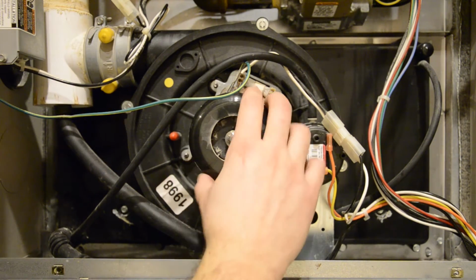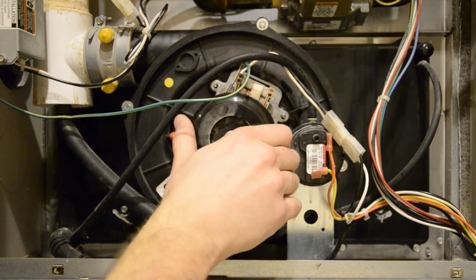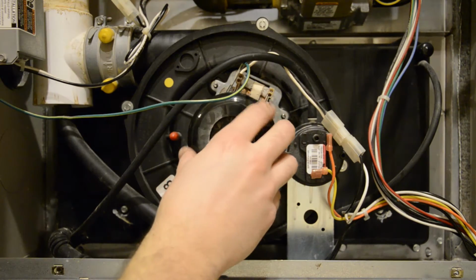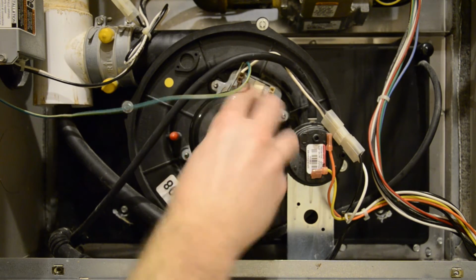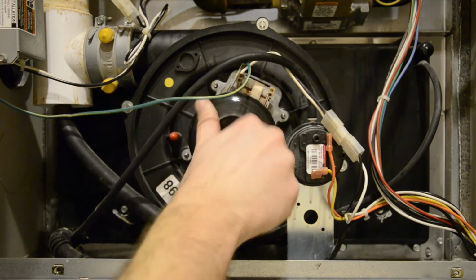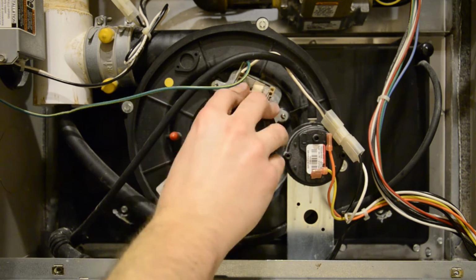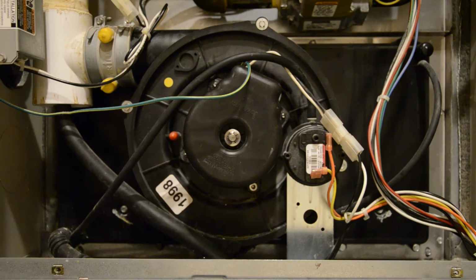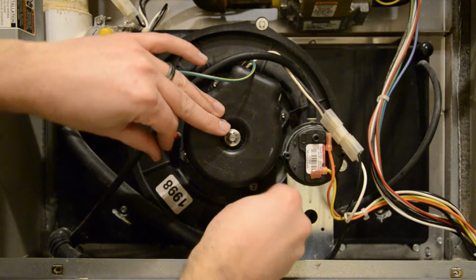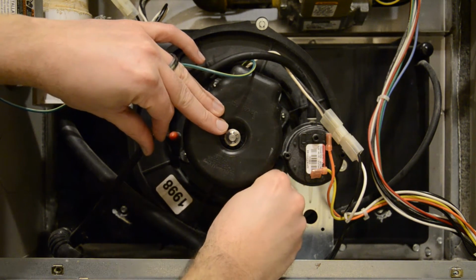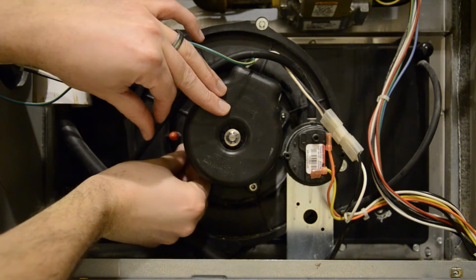Try turning the motor to see if it's stuck. If not, you may be able to temporarily reseat the bearing by turning the motor many times and retightening everything. Put the cover back on and reinstall and tighten the 4 nuts. Then turn everything back on and test to see if this works.